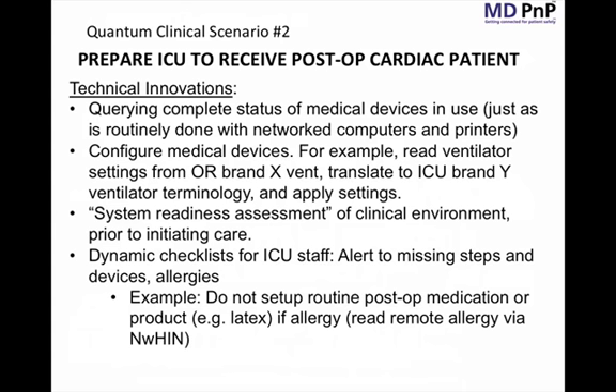A different set of complexities arise when one is transferring ventilator settings. Not all ventilators have the same settings. They don't all have the same modes, so to speak. And the modes have different names, which are typically proprietary and are different for each manufacturer. Therefore, the ICU ventilator may have a mode that does not match up in name to the ventilator that's used in the operating room. Therefore, we have to translate these terms or modes from one ventilator to another and ensure that we're doing so in a way that will be equivalent from a clinical standpoint. That poses an interesting and unique challenge.